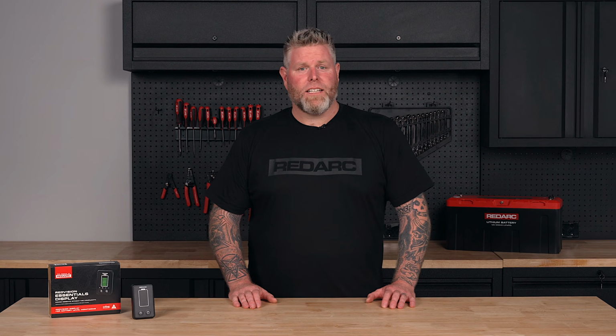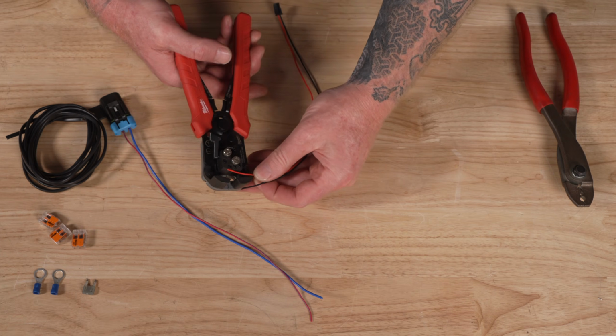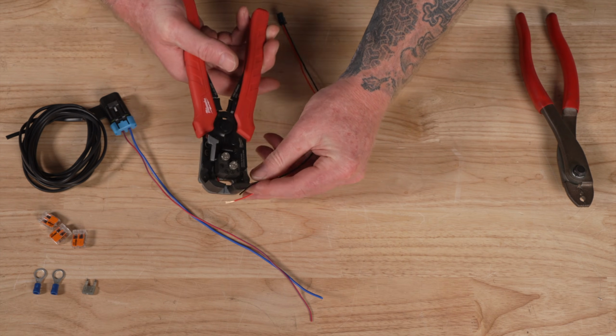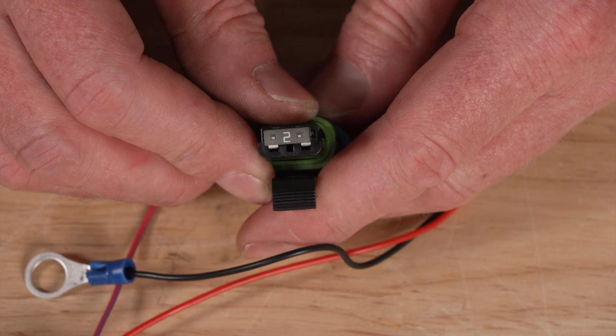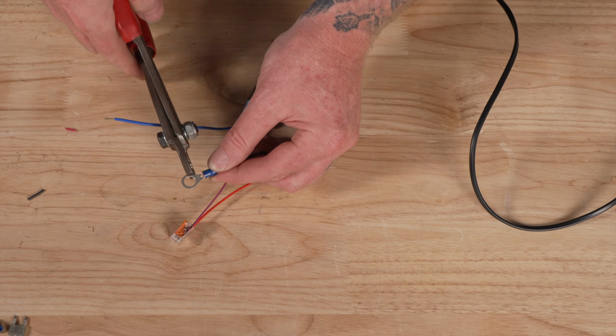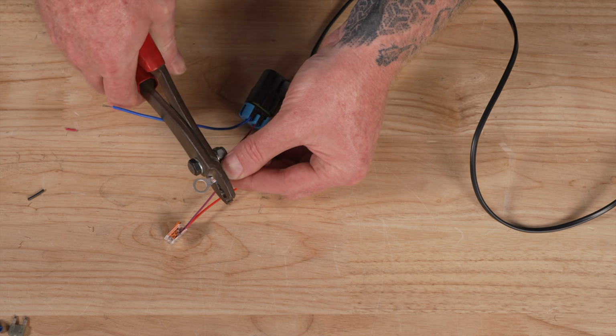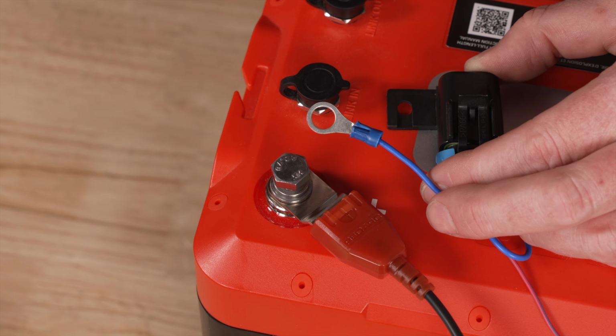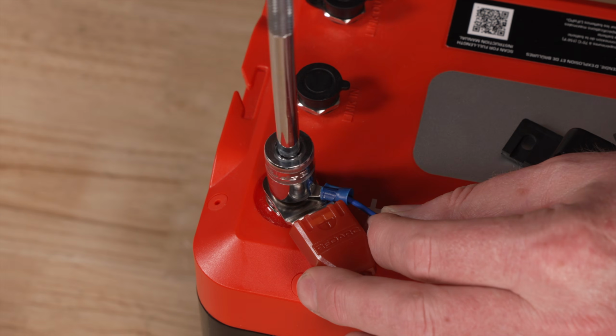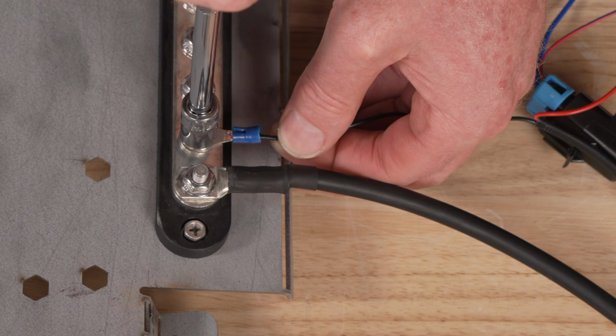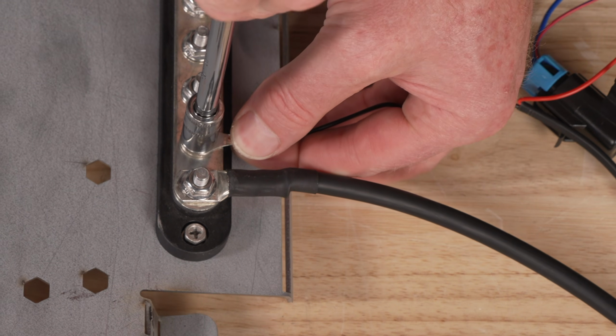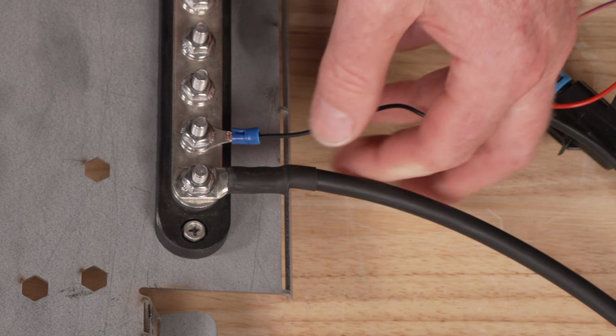If the display isn't connected to a powered R-bus cable, we'll need to connect the display to power. Extend the red and black wire with a minimum wire size of 0.5mm squared, fused with a 2A fuse, and fit with a ring terminal suitable for connecting to your battery's positive terminal. Ensure that the fuse will be mounted as close as possible to the secondary battery. Then connect the black wire to a suitable chassis ground or the GND terminal of the smart battery monitor.